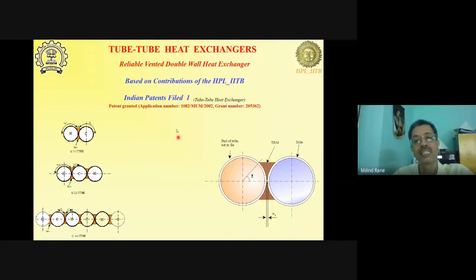So this is a tube heat exchanger patent, which we have. As I said, we can have two tubes put side by side with a thermal bonding material. The thermal bonding material depends on the tube material itself. I can have copper, and then this could be brazed with a copper brazing alloy. If I have stainless steel and copper, then I will need a silver alloy, which is unaffordable. So we have different thermal bonding materials which we use for different applications.